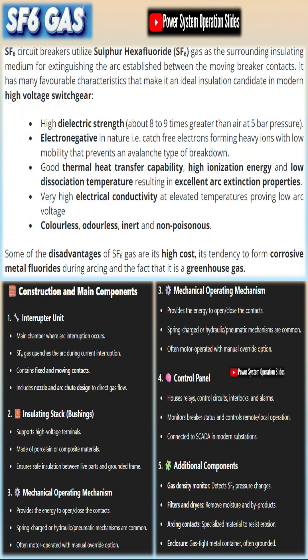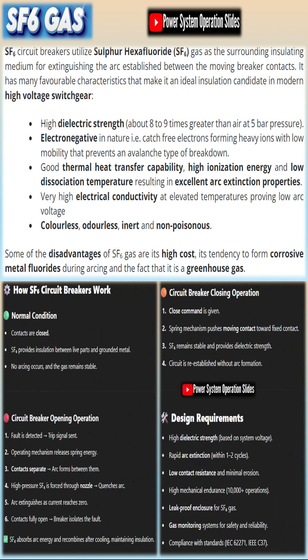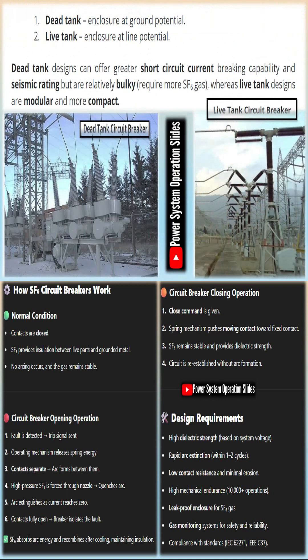Molded case technology with air at atmospheric pressure is used at low voltages, whereas air blast and vacuum circuit breakers are prevalent at medium voltages. SF6 circuit breakers are normally used for high voltage systems.